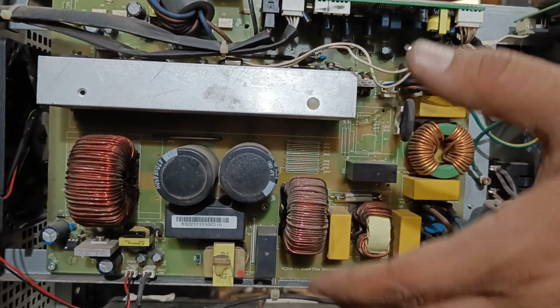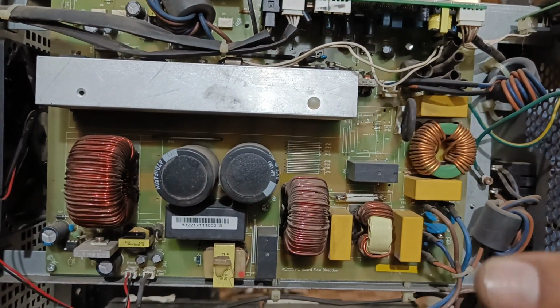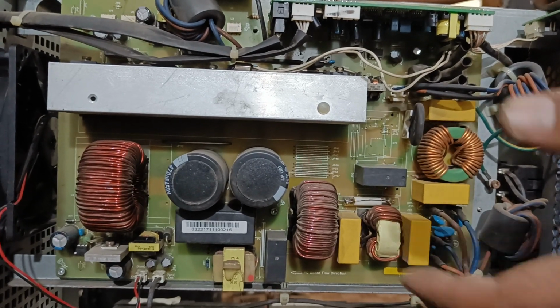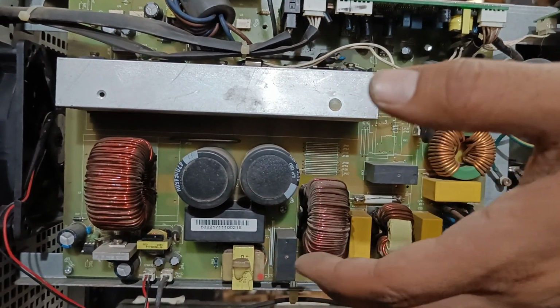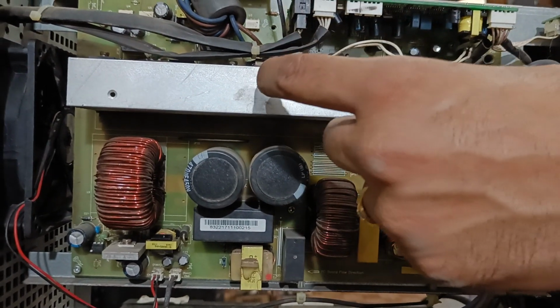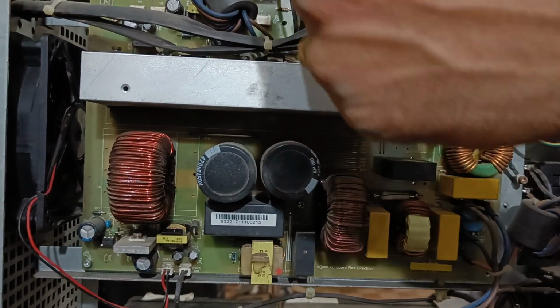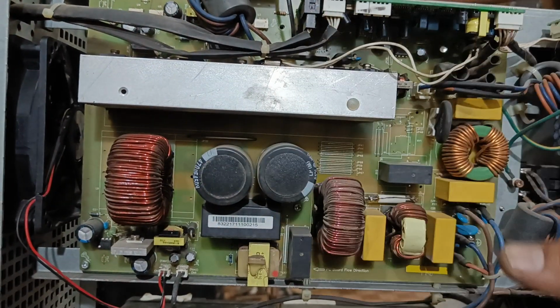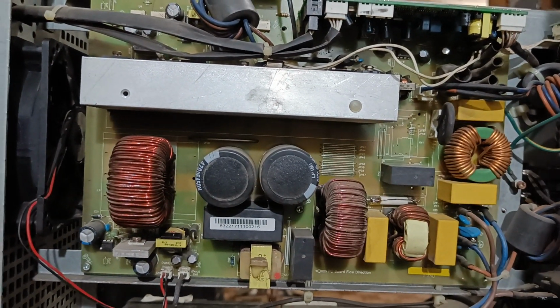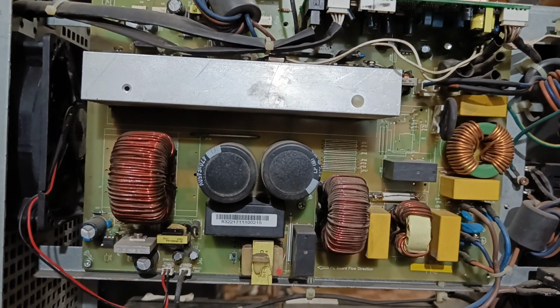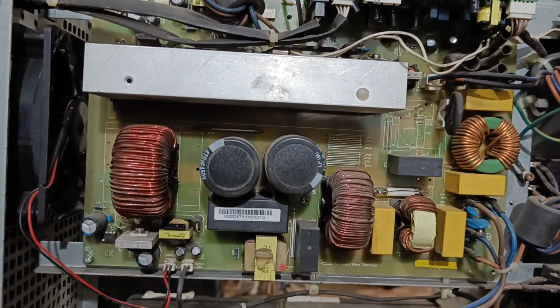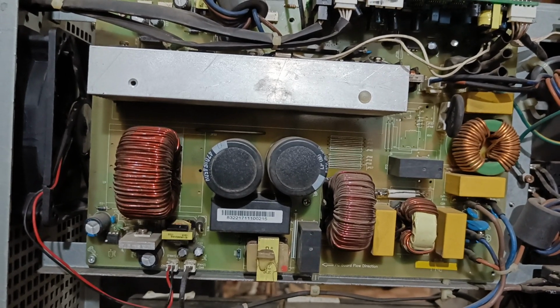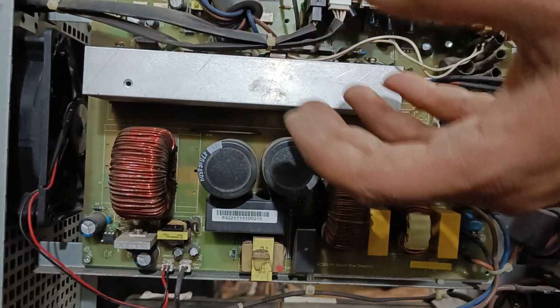And this is the input PFC section, power factor correction. While the UPS is running on input, when we give it the main supply, the UPS runs on the input PFC section. This section helps run the UPS inverter on mains mode, and on battery mode the UPS gets voltage from the MOSFETs. But at the input side, when we give input, the inverter gets voltage from here.